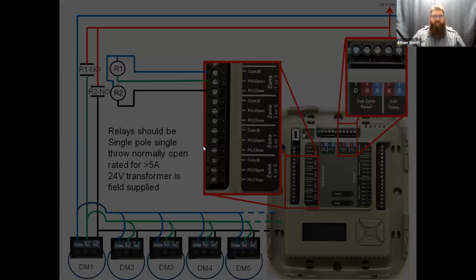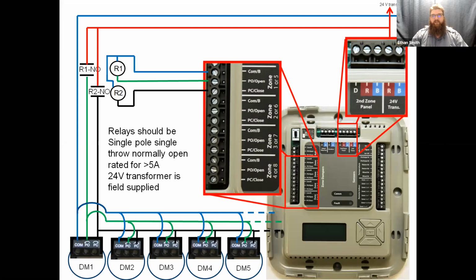So we mentioned up to 4 dampers, you just wire them in parallel. If you need to go above 4 dampers, that's an example of what you can do. You just need to put in some isolation relays. Make sure that you're powering them off so that when it goes to power the damper closed, it's going to hit that relay 1, and it's going to close that set of contacts and power open all of your dampers at once. So as many dampers as you want. I have had a zoning system that I worked with a guy on that had 16 dampers on one zone. So it is possible. Just got to make sure your relays are sized for it, and we need to isolate them so that we don't burn up the relays in the zoning board.